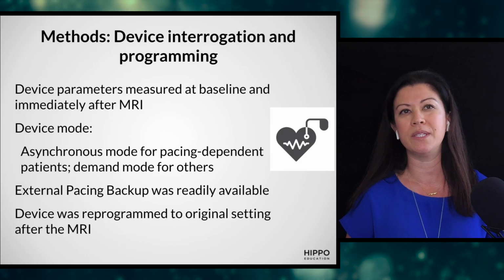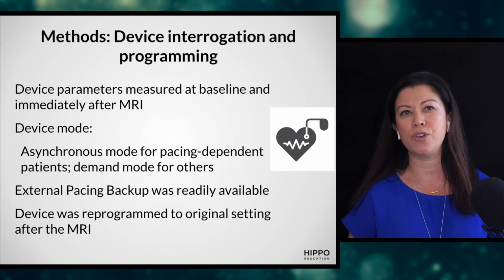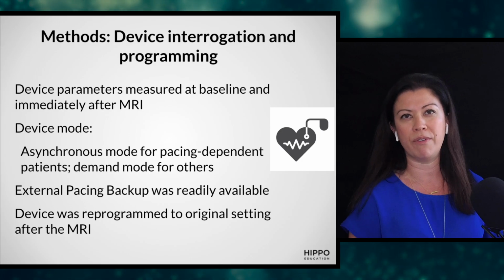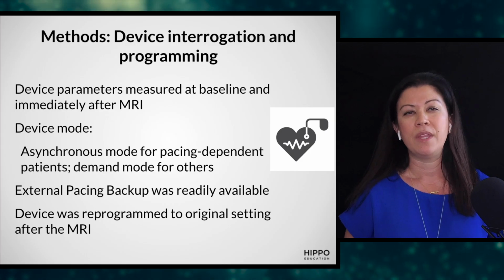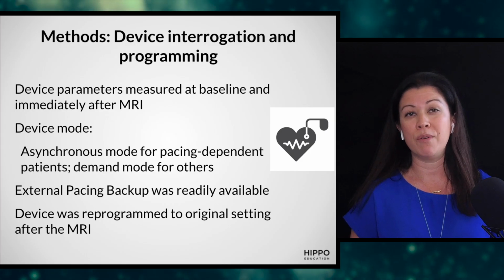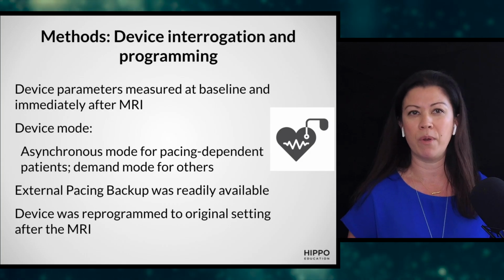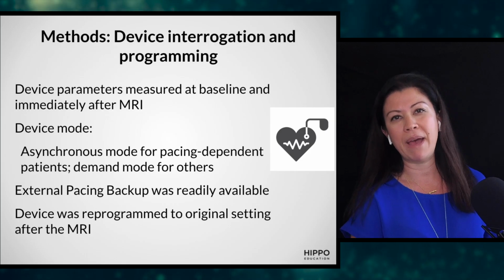What is important, though, is that the device parameters were measured both at baseline and immediately after the MRI. They wanted to make sure that the device was interrogated consistently before and after. They would put the device in asynchronous mode for pacing-dependent patients and on-demand mode for everyone else. And most importantly, they did external pacing backup just in case. And why is that important?